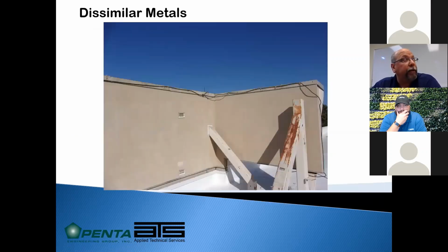And we see this routinely with copper that's attached to metal coping on parapet walls. There are a lot of other things wrong with this picture and the way this was maintained, but the main goal for this was copper on metal coping. We see this many, many times, and it needs to be replaced. This should be aluminum everywhere the conductor is in contact with metal. And then the aluminum can transition back to copper where it runs across the roof and is not in contact with metal.